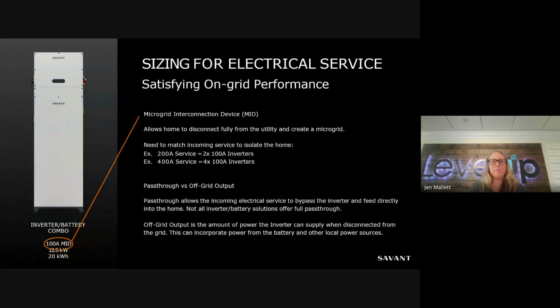Here's a good example of sizing for electrical service. A microgrid interconnection device, or MID, allows the home to disconnect from the utility—that's what enables the microgrid. But we need to match the incoming service that was originally provided by the utility. So, for example, a 200 amp service would equal 2 100-amp inverters, and a 400 amp service would equal 4 100-amp inverters.